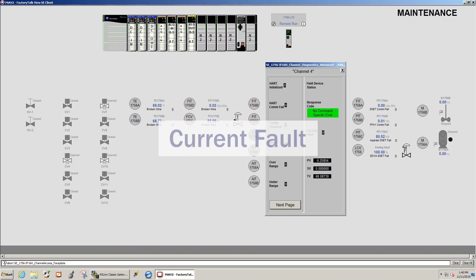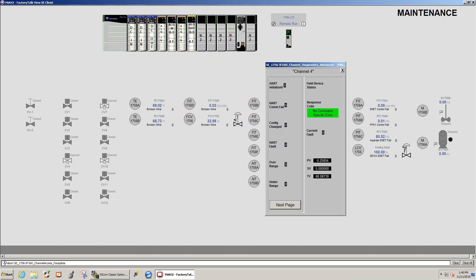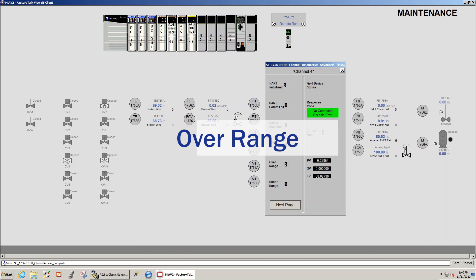Current fault, analog current measurement does not match the current that the field device reported over the HART network. Then the two non-HART variables that we are tracking are over range, we have a signal value over range, typically this is over 20 milliamps, under range.